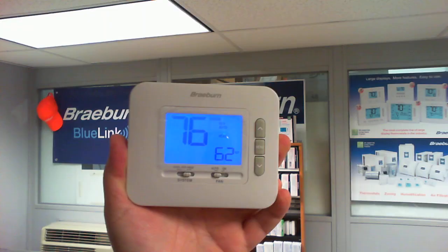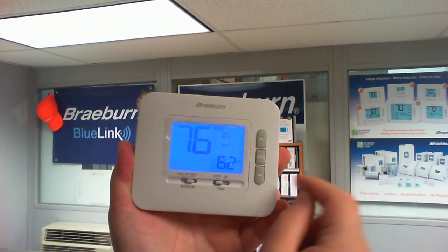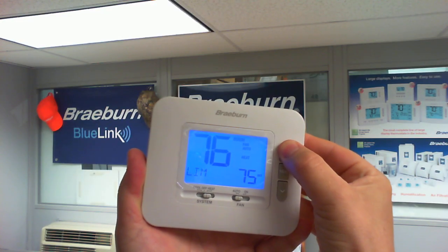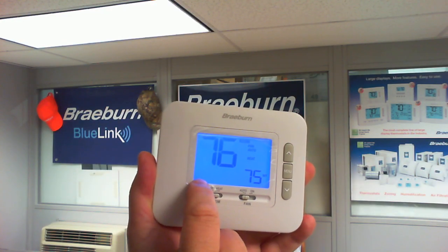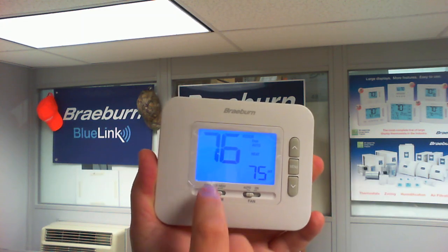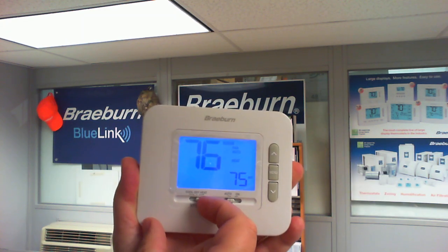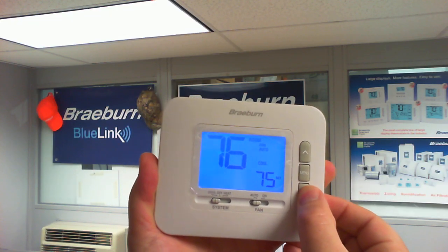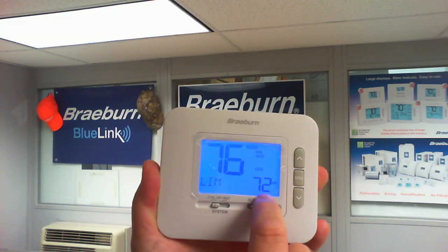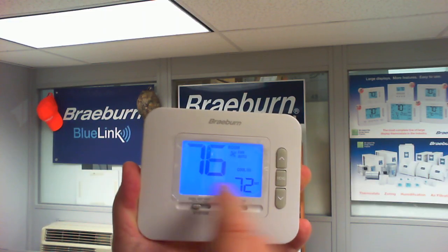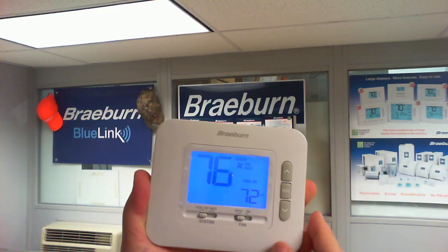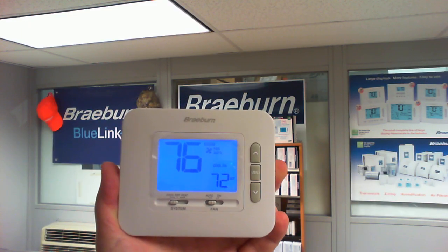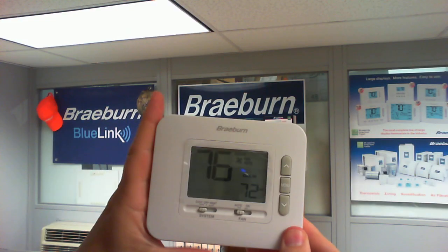Back. Now we're back to operating. So we're in the heat mode. If we try to raise our heating up, we can only go to 75, and then it says lim, indicating that we've hit the limit. Same thing if we put it in the cooling mode. We won't be able to lower the cooling less than 72. That was the limit that we had set, and it will pop up lim when you hit that. Your user can no longer get into the installer menu to make those changes because you put the lock.